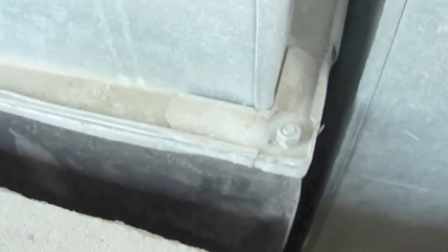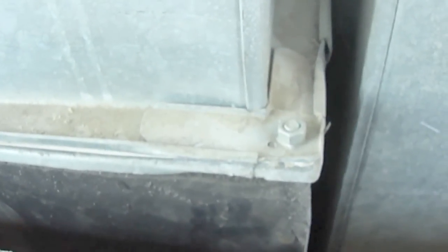And at the time of soldering and fabrication, you need to be very careful. You need to cross check this joint, because if you do not cross check this, you can find maximum leakages with the seams compared to the flanges. Fine. Anyhow, flanges will have the gasket, but if the seam joints are not properly fabricated, they will give you a lot of pressure and air loss, meaning leakages. And again, what about this flange?